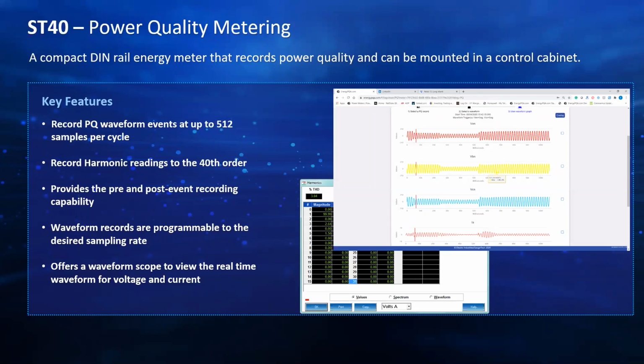Power quality metering, up to 512 samples per cycle, harmonics up to the 40th order, events that can be recorded. I was saying for voltage, current, we can record waveforms, but for frequency, power factor, harmonics, we can set up alarms. The alarms will record the date and time that event happened, what happened, whether it was a low power quality event, a high frequency event. It will tell us how high the frequency went or how low the power factor dropped to, and it will tell us how long that lasted, whether it was 1 second, 10 minutes, a day. All of that gets recorded inside the meter.